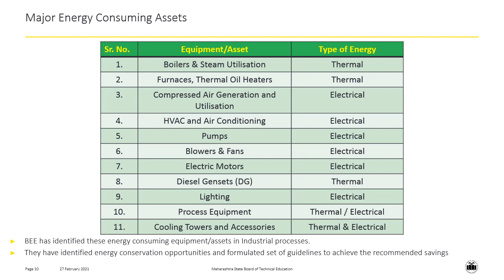In this slide, we are going to learn about the different energy conservation opportunities or different techniques of saving energy as suggested by the Bureau of Energy Efficiency. In boilers, we can use the air preheater as well as economizer, minimize incomplete combustion, reduce excess air, as well as reduce the heat losses through proper insulation, using automatic blowdown control, and replacing the boilers after every 25 years of use.